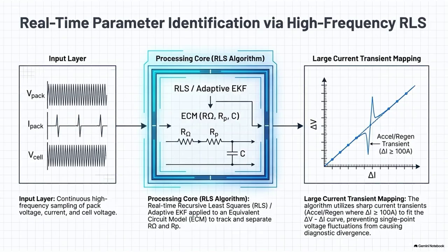Yes, but, and this is the genius part, it doesn't trust every measurement equally. The filter maintains covariance matrices, which is essentially a mathematical measure of uncertainty. It literally calculates how sure it is of itself. Exactly. It has a process noise covariance representing how much it trusts its own internal math model, and a measurement noise covariance representing how much it trusts the physical sensors. So if the motor is spinning up and throwing off tons of electrical noise, because the motor inverter introduces that high-frequency noise, the adaptive mechanism dynamically tunes these noise matrices. If it detects high levels of electrical noise, it says, I don't trust the sensors right now, and it relies more heavily on its internal model.